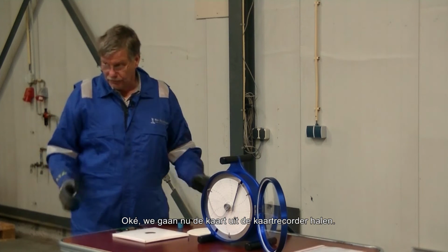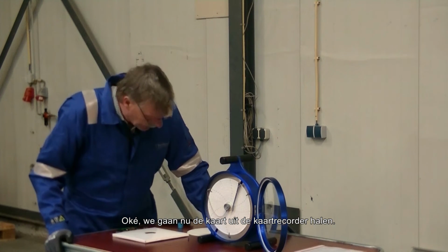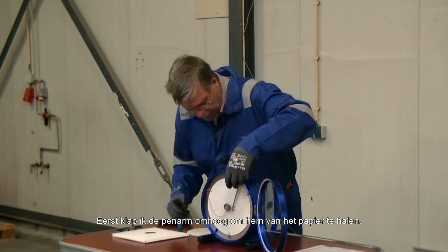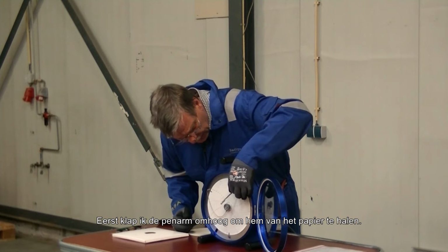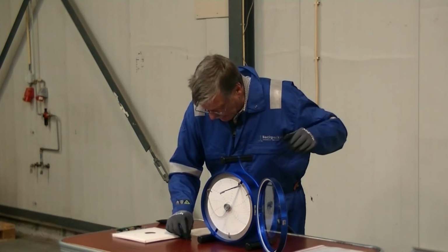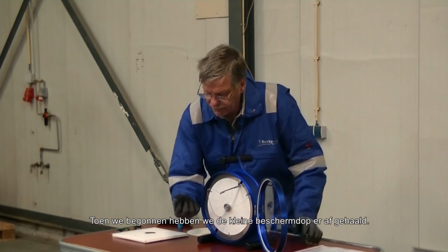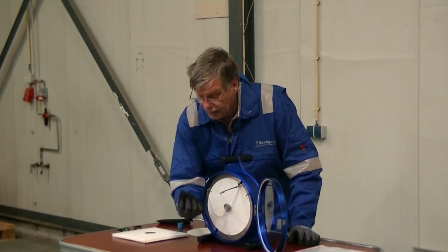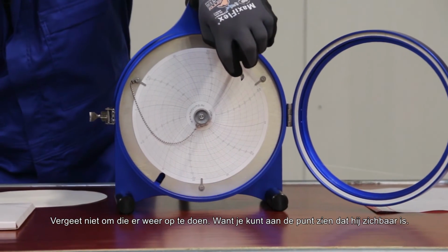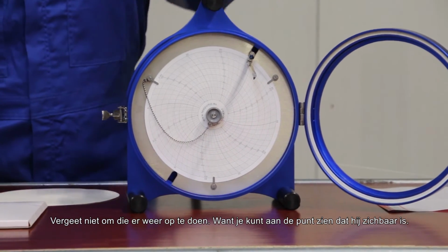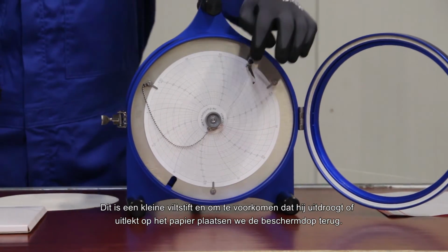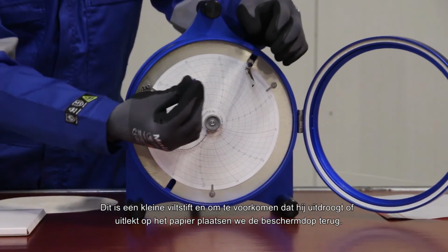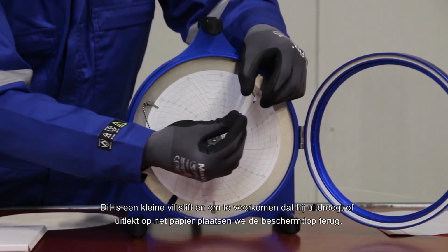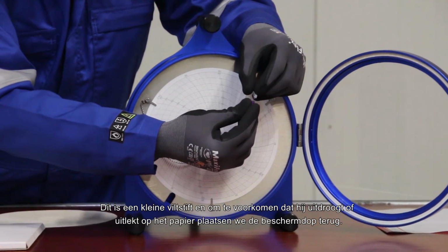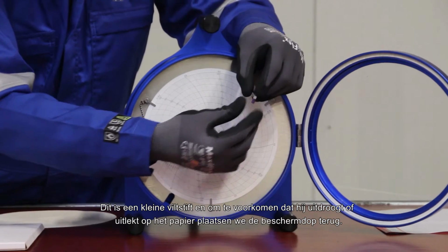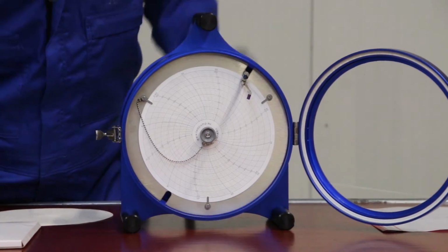Okay, we're now going to retrieve the chart from the chart recorder. First, I'll flip up the pen arm to take it off the paper. When we started, we'd taken off the small protector. Don't forget to put it back in there, because you can see at the tip there that is exposed. This is a small felt pen, so to prevent it from drying out or draining out on a piece of paper, we replace the protector.